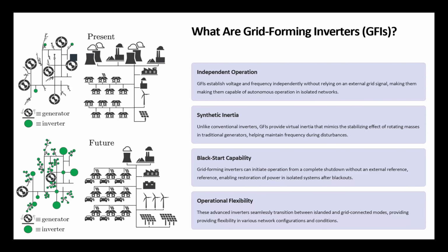The second solution is to use the power electronics of renewable energy sources or batteries to create frequency and ensure its stability, even without rotating machines, by mandating the frequency and voltage level as the rotors do. These equipments would basically become the conductors, and the other renewable energy sources would just have to follow the scores. This solution is called grid forming.